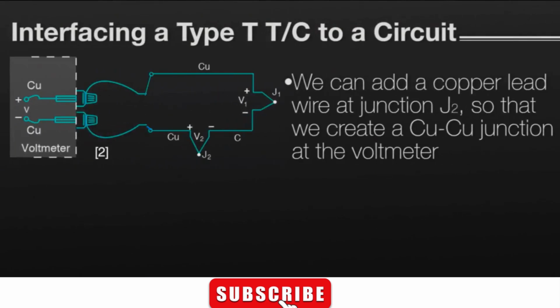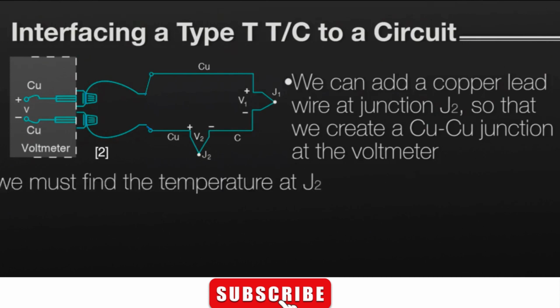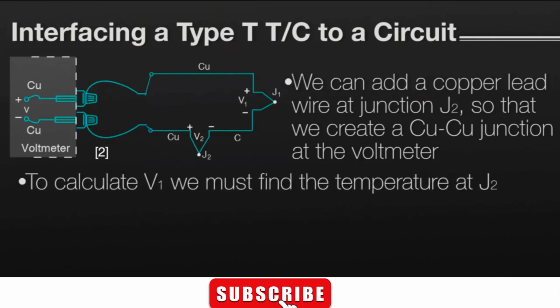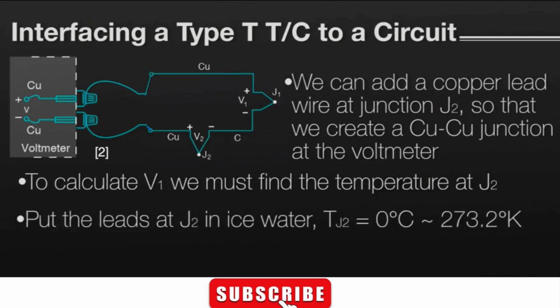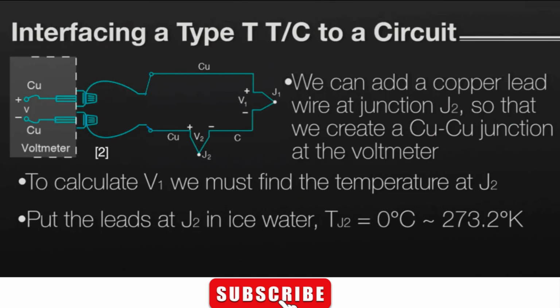I'll take care of you. Let's add a copper lead wire at junction J2 in the picture. This way, at least, we'll have standard copper-to-copper connections at the voltmeter. To calculate our thermoelectric voltage V1 at junction J1, we must first know the temperature at junction J2. Now, 50 years ago, people really did this by putting the leads of the dissimilar metals at junction J2 in a bucket of ice water. This forced the temperature at J2 to exactly 0 degrees C, and the term ice point reference was born.